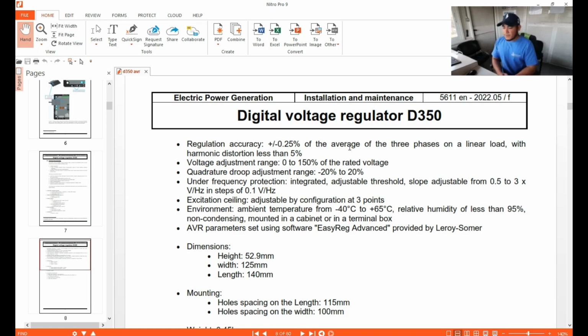Always they refer to the rated voltage, which is the voltage you are using, the output voltage of your alternator. So that is a range of 0 to 150%. The quadrature droop adjustment ranges from minus 20% to positive 20%, standard at 1. For excitation, the under frequency protection is integrated with an adjustable threshold of 0.5 to 3 times volt hertz, in steps of 0.1 volt hertz. So if you rotate it, it can be set at 0.1 for every turn of your potentiometer. Excitation ceiling is adjusted by the configuration at 3 points.